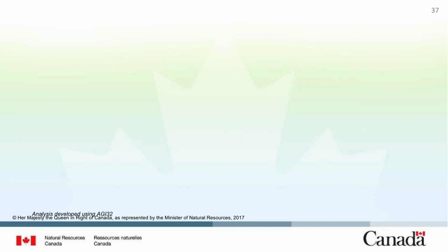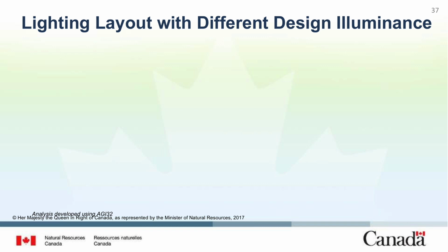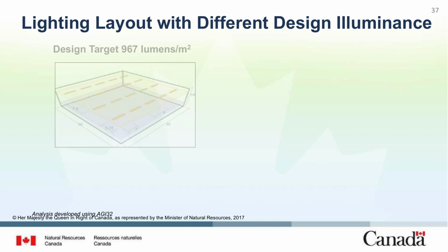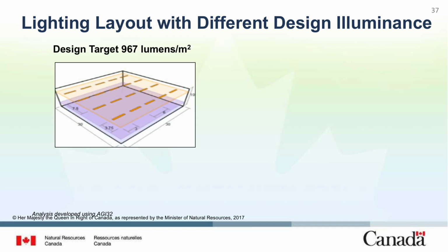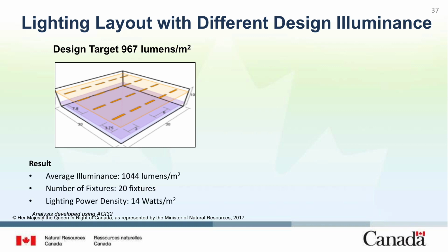Here is a case study to illustrate the impact of lighting redesign considerations. On the left-hand side, there's an image of a traditional layout of an older facility. Facilities built before we had computers, so any facility before 1970, were designed for drastically different illuminance levels. The example on the left has an illuminance level of 967 lumens per square meter. You can see that in this design, 20 light fixtures are required to meet the required illuminance level.